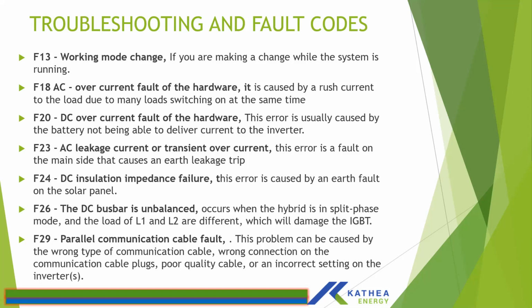And then the parallel communication cable fault. If your cable is not properly crimped, then you would have this alarm, or you have connected on the wrong ports, or you have a poor quality cable, then you would have this fault. But mainly within the system, the fault will be caused by incorrect settings on the inverter. For an inverter in a single phase, in settings you set the master on phase A and the slave on phase B. So the slave would definitely give the fault to say, I'm a slave, but I don't have a master in my line. So these are some of the most common faults that you'd experience.